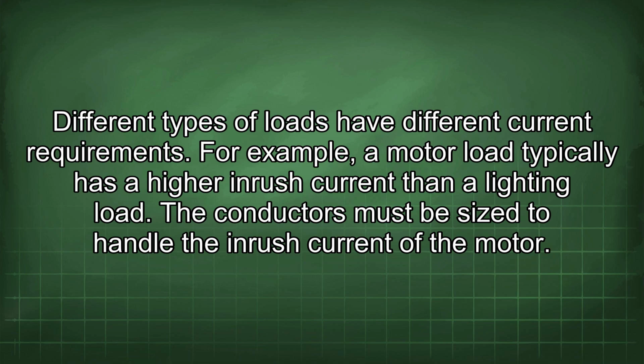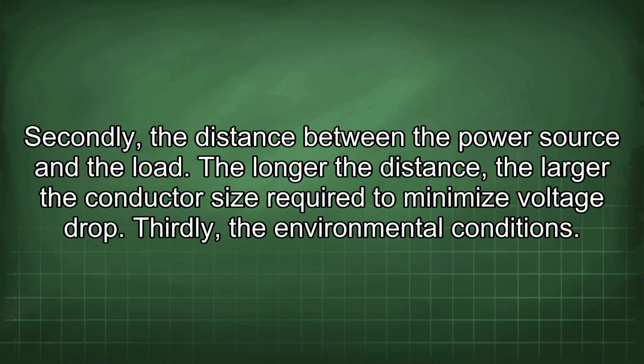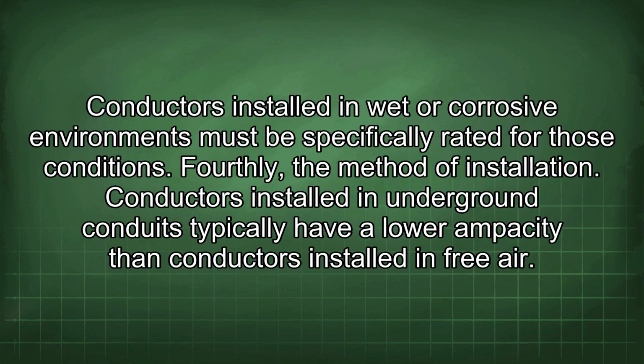The conductors must be sized to handle the inrush current of the motor. Secondly, the distance between the power source and the load. The longer the distance, the larger the conductor size required to minimize voltage drop. Thirdly, the environmental conditions. Conductors installed in wet or corrosive environments must be specifically rated for those conditions. Fourthly, the method of installation. Conductors installed in underground conduits typically have a lower ampacity than conductors installed in free air.